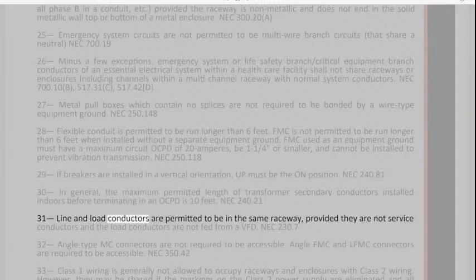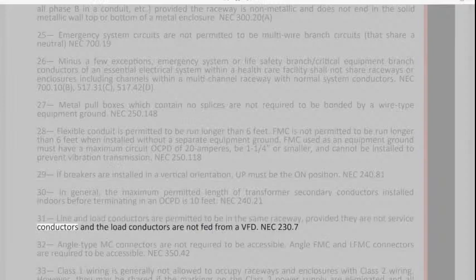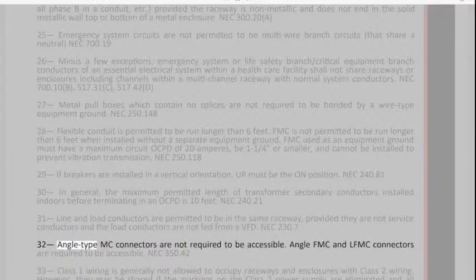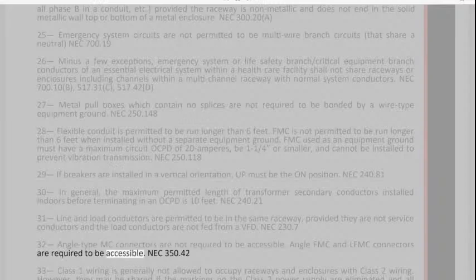31. Line and load conductors are permitted to be in the same raceway, provided they are not service conductors and the load conductors are not fed from a VFD. NEC 230.7. 32. Angle-type MC connectors are not required to be accessible. Angle FMC and LFMC connectors are required to be accessible.